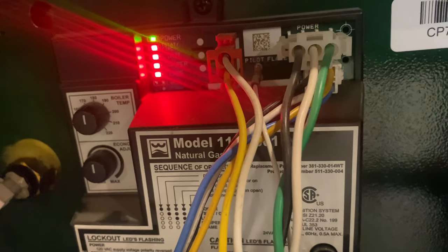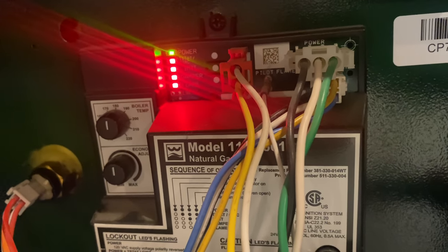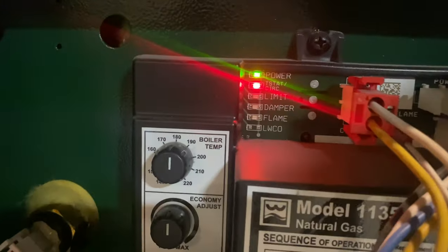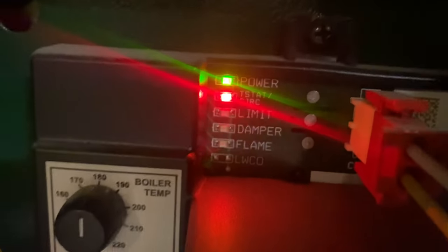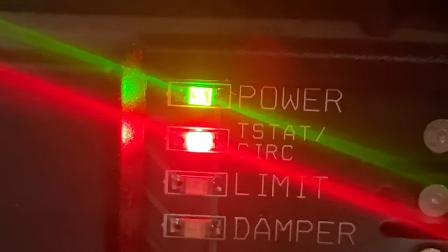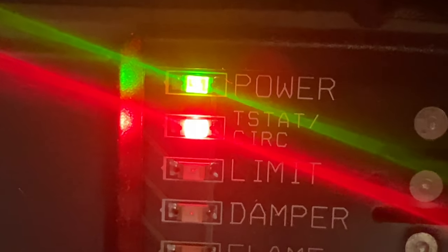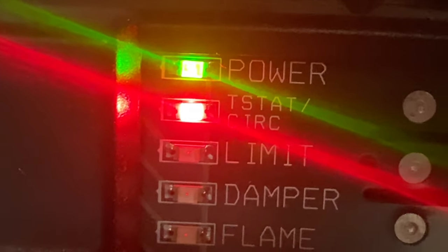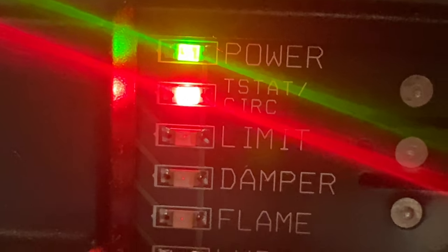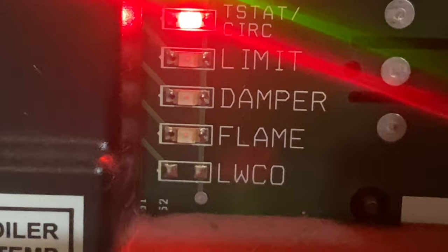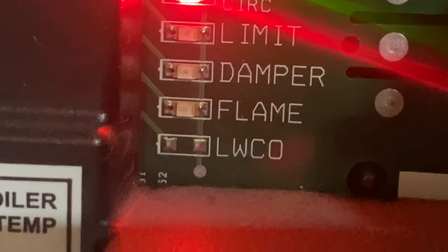When we came it was already on, so I don't know how long it's been on. We'll find out shortly. If we zoom in, you're going to see that the green power light, which is normally on, is illuminated. The red light, which stands for the thermostat circulator, is powered. But our limit, damper, flame, and low water cutoff are all off, and the boiler's not running.